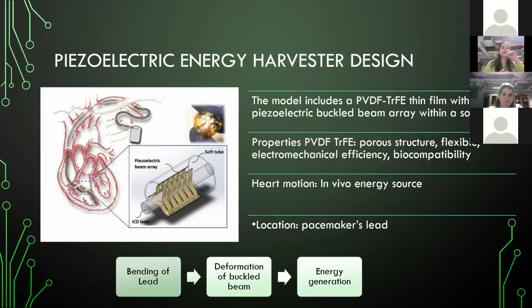The source of energy in this design is considered to be an in vivo energy source. It's the heart, or cardiac motion, which is considered one of the most captivating in vivo energy sources for harvesting cardiac energy. As we can see in the picture, the design is mounted on the pacemaker's lead, and the purpose of this design is to charge the pacemaker's battery by converting the mechanical energy generated from the cardiac motion into electrical energy. In fact, the bending energy of the pacemaker's lead causes the deformation of the buckled piezoelectric beam, which results in the generation of an electrical current.